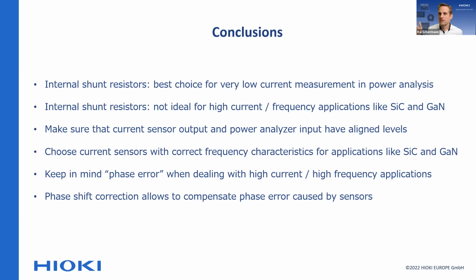When, after the third harmonic, your current sensor doesn't provide adequate data - where's the point, basically? It's very important to keep in mind the phase error when dealing with high current and high frequency applications. It's a phenomenon you have with every current sensor, and also with shunts, but especially with high power, high current applications, you need to keep in mind the phase error you're creating. That phase error is a physical phenomenon - it's nothing you can reduce to zero. Only in a physics book at school does a current sensor not have a phase error. In reality, it's physical - you cannot avoid it. Every current sensor has that. The question is how well this phenomenon is dealt with.